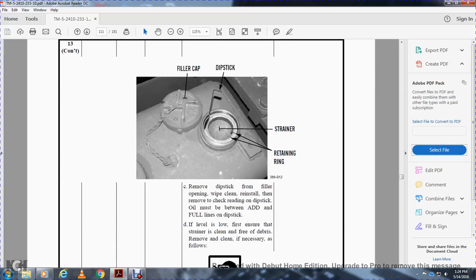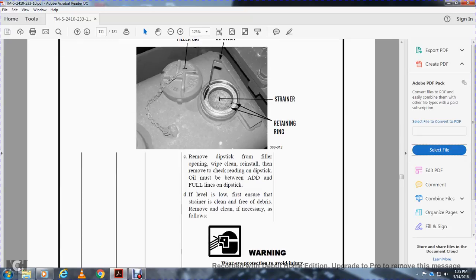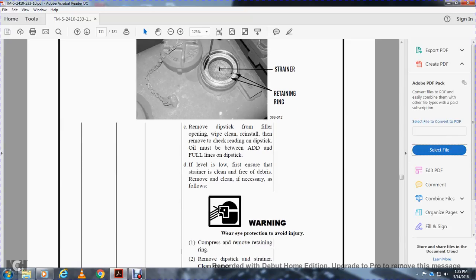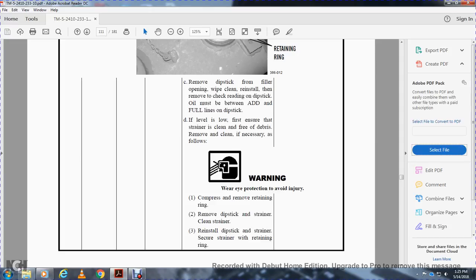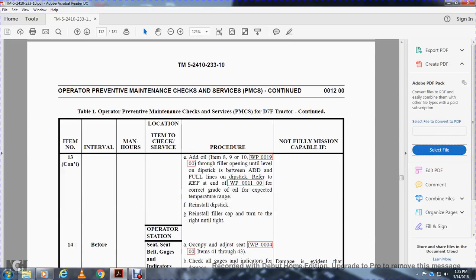Remove the dipstick from the filler, wipe it clean, reinstall it, remove it, and check the reading on the dipstick. Oil must be between the add and full lines on the dipstick. If the level is low, check the strainer and clean it free of debris. Remove and clean if necessary. Warning: wear eye protection to avoid injury. Compress and remove the retaining ring. Clean the strainer. Replace the strainer and secure it with the retaining ring. 13, continued.